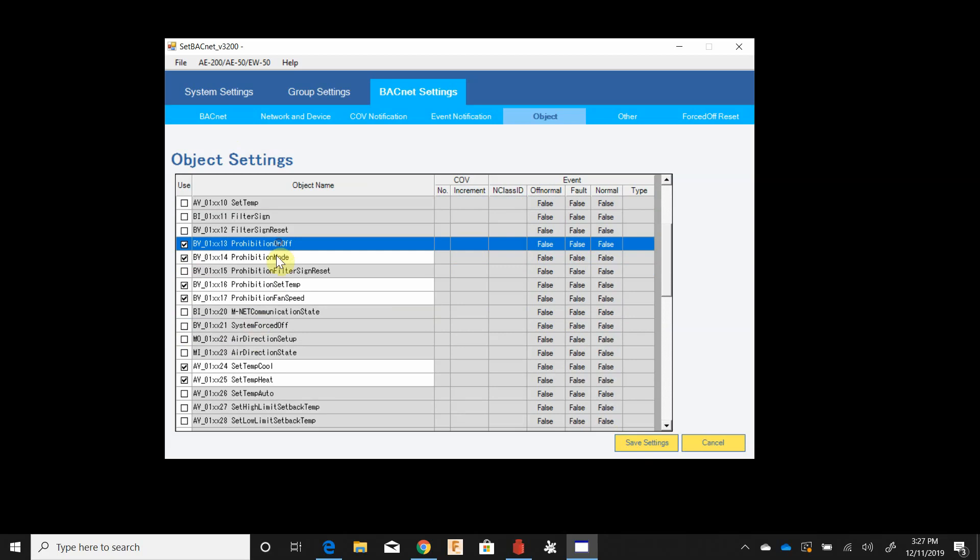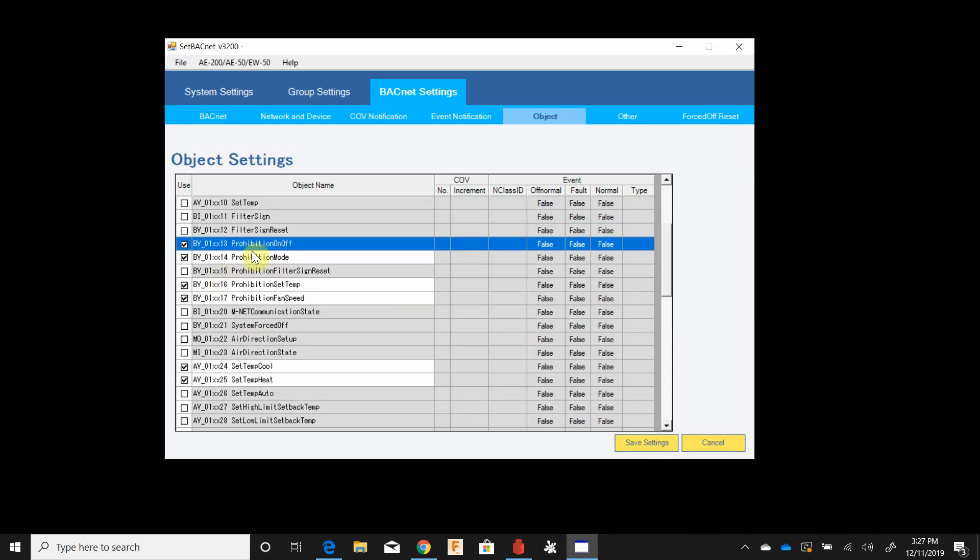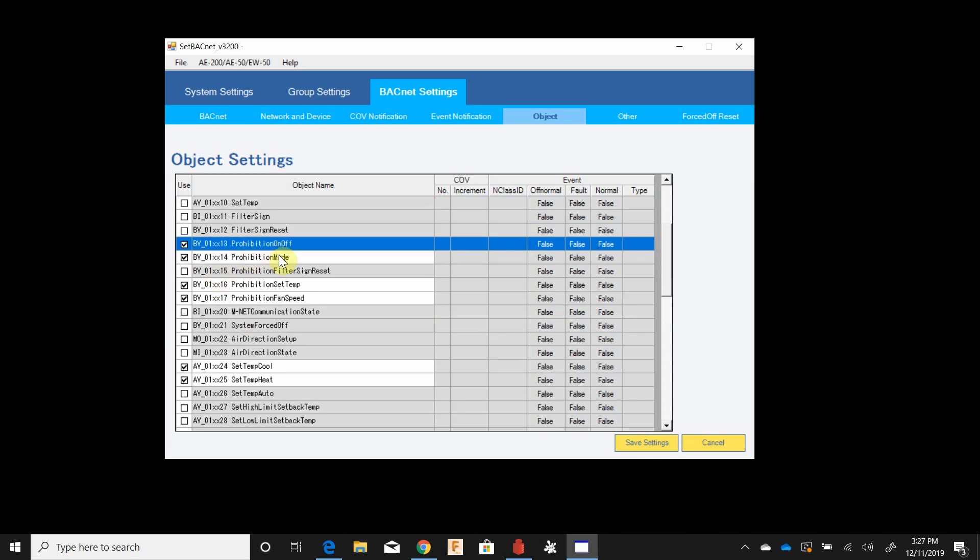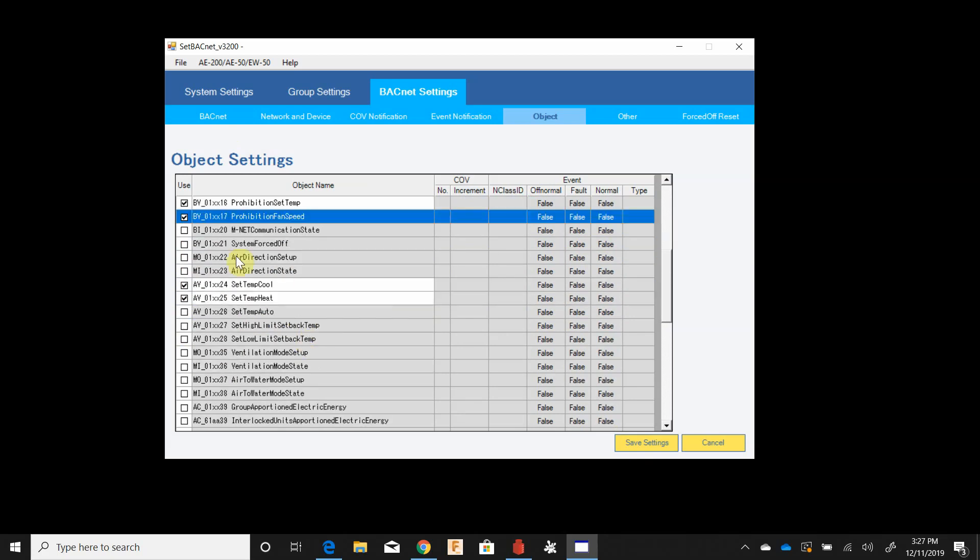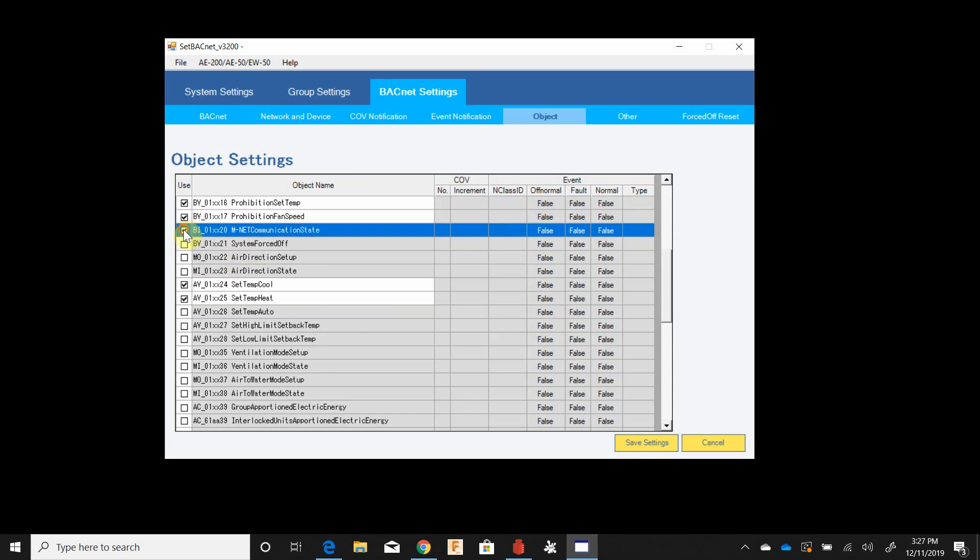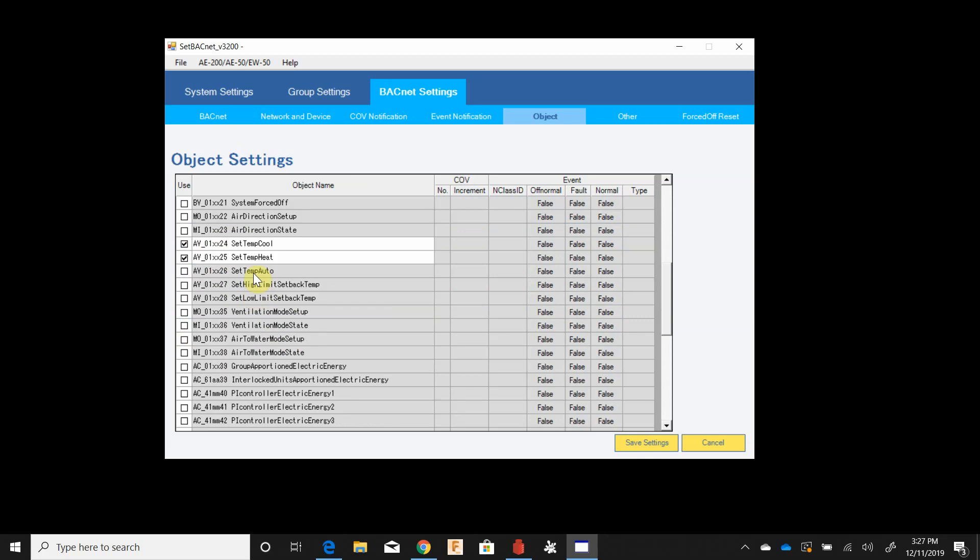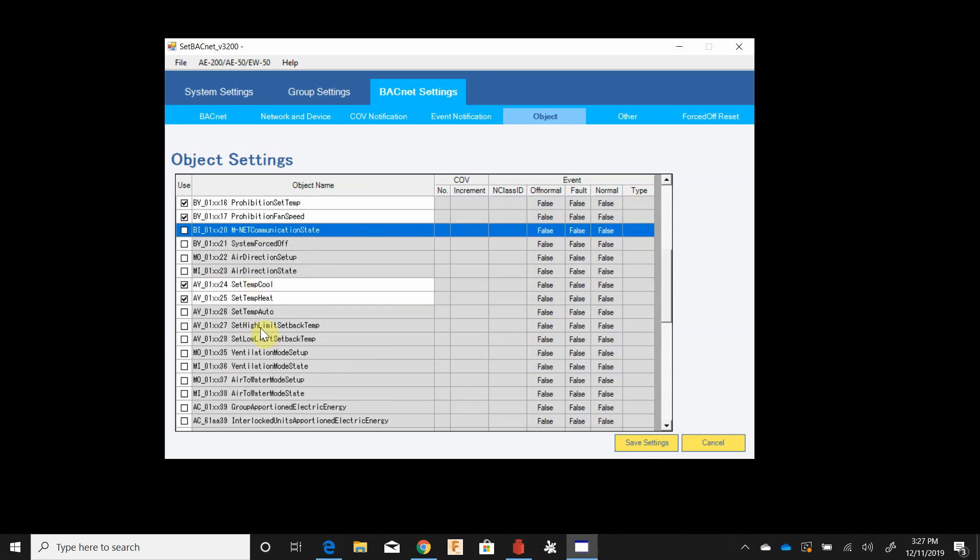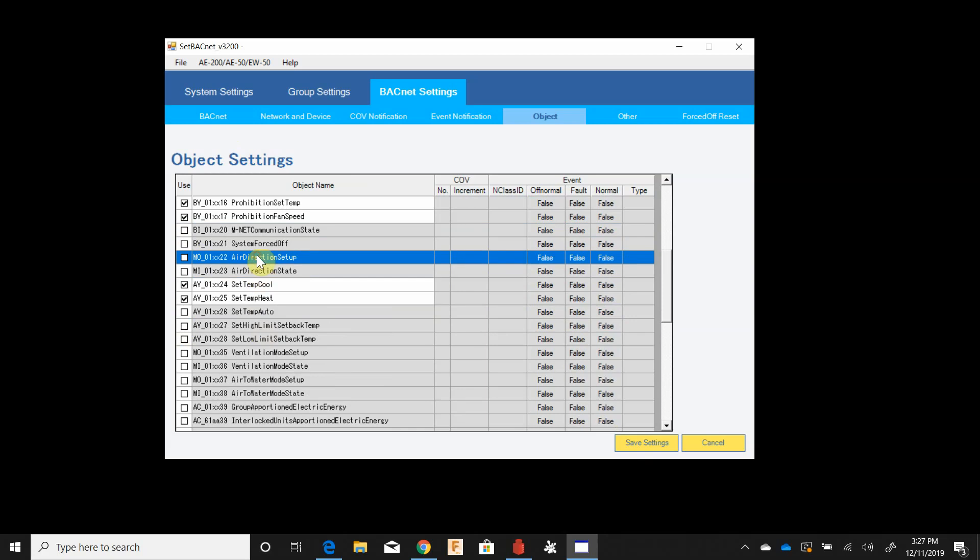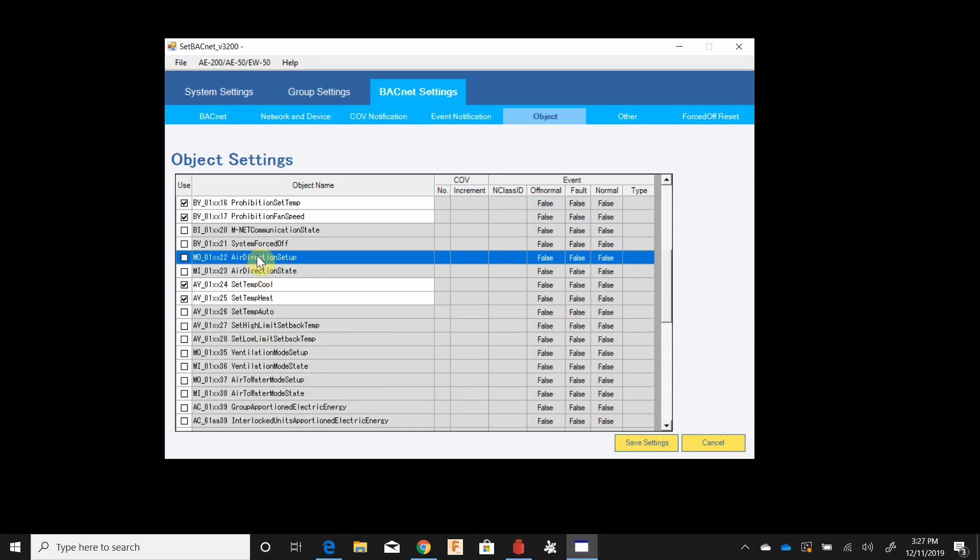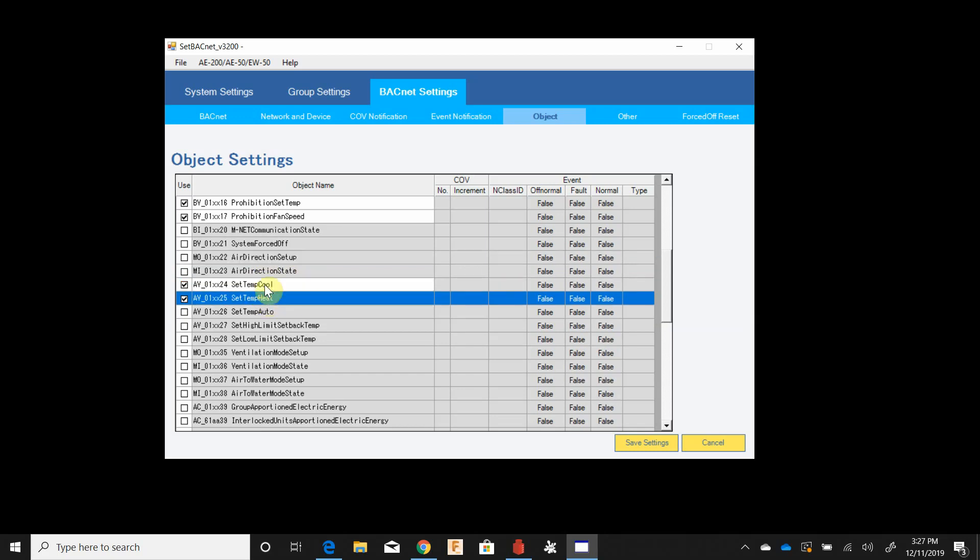Prohibit modes allow the building automation contractor to lock out operation at the thermostat of certain items. Our MNET communication state, well they'll get an error code anyway so we'll leave that one unchecked so they're not getting overloaded. Air direction I like to leave this one up to the thermostat itself that way the end user can control the vanes instead of the building automation contractor doing that.